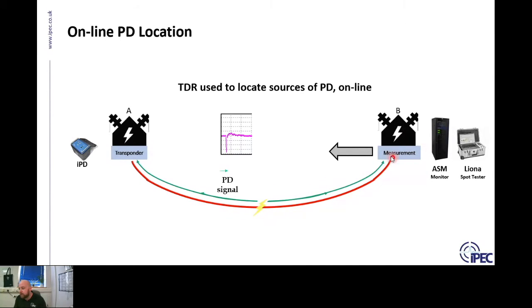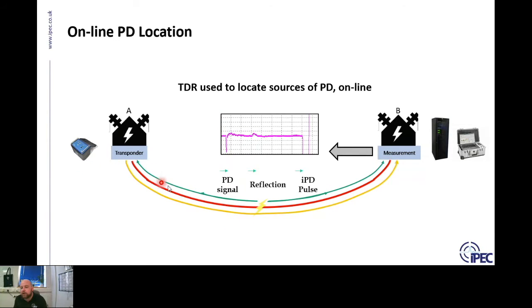So the first thing the measurement device will see is the initial PD that has occurred. Now at the same time, in this case because the PD is perfectly in the middle of the cable - which never happens - at the same time the transponder unit has detected the PD. Now that transponder unit will trigger on the PD and it will send a large pulse down the cable.